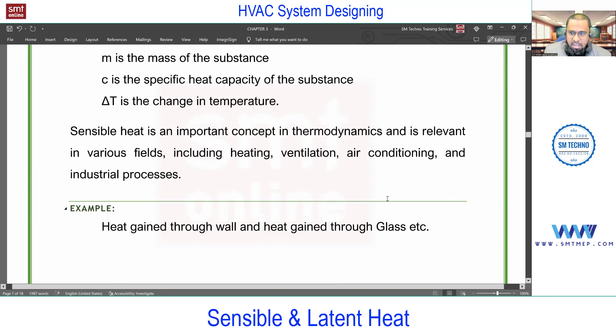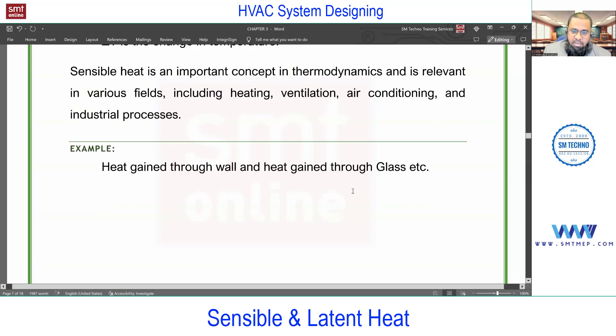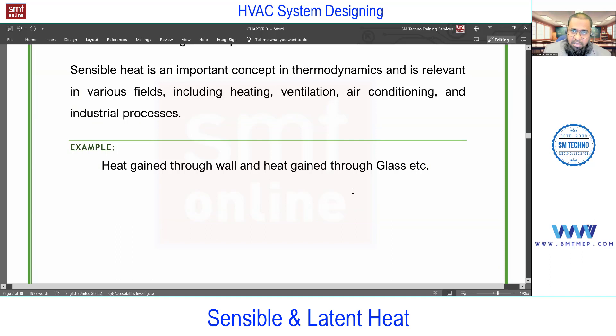Heat gain through wall and heat gain through glass can be considered as sensible. This is very important throughout load calculation — for all possible sources we check whether the source involves conduction, convection, radiation, and whether it is sensible only or sensible plus latent. According to that we have the calculation. This manual load calculation is the basic foundation for software load calculation.